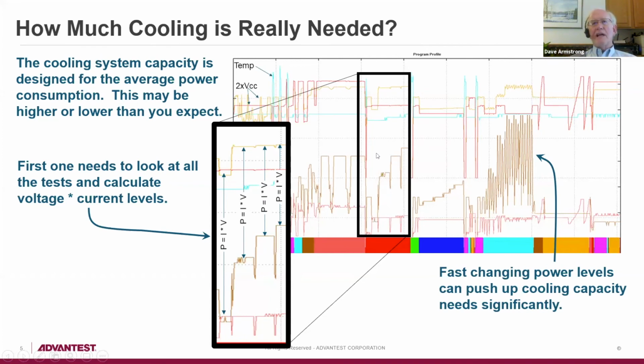Being able to handle this as I size my cooling system appropriately is key. If I were to just size it based on power consumption, you'd say it's the duty cycle times the voltage times the max current. But that won't get you where you need to go. You need the added capacity for this.